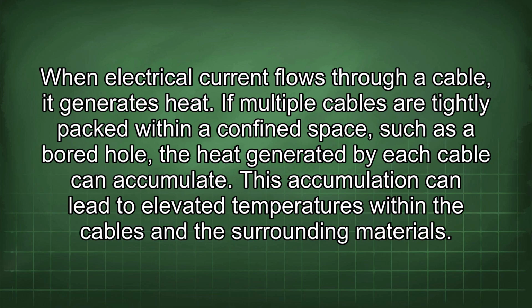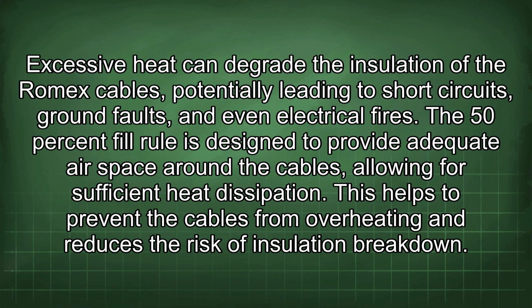When electrical current flows through a cable, it generates heat. If multiple cables are tightly packed within a confined space, such as a bored hole, the heat generated by each cable can accumulate. This accumulation can lead to elevated temperatures within the cables and the surrounding materials. Excessive heat can degrade the insulation of the Romex cables, potentially leading to short circuits, ground faults, and even electrical fires. The 50% fill rule is designed to provide adequate airspace around the cables, allowing for sufficient heat dissipation. This helps to prevent the cables from overheating and reduces the risk of insulation breakdown.